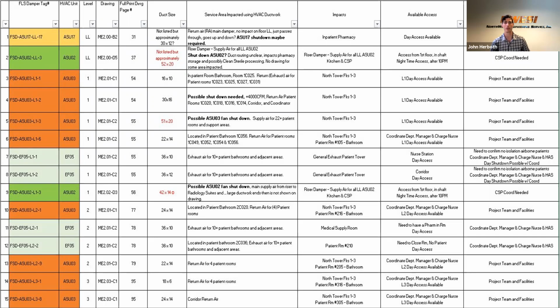So you do your best coordination, and you can find some side impacts that are going to be really troublesome. You end up trying to take a look at airflow quantities, making sure that when you're testing these individual fire dampers or fire smoke dampers, you don't shut down a piece of equipment due to high static or low static.